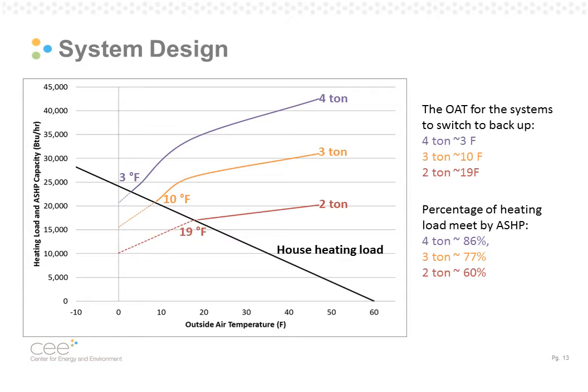So if you look at the chart, on the x-axis you have the outside air temperature, and on the y-axis is the heating load of the home and the air source heat pump capacity in BTU per hour. The black line is the home's heating load, while the red, orange, and purple lines are the equipment output, and this was based on manufacturer provided data for a 2-ton, 3-ton, and 4-ton unit. If the system was programmed to be switched to the backup, so switched to the furnace, when the heat pump could no longer meet the full heat load of the home, the 2-ton switches over at 19 degrees Fahrenheit, while the 4-ton unit switches over at 3 degrees Fahrenheit.